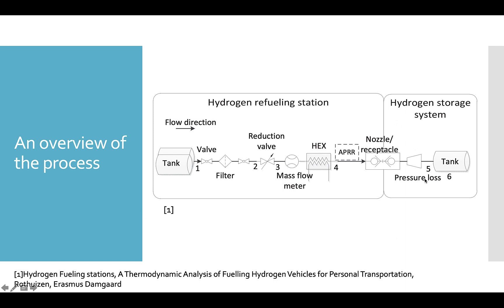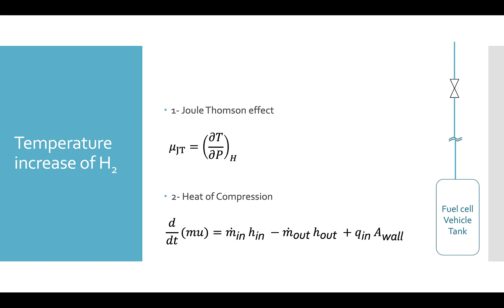In this process there are two points which increase the temperature of the hydrogen. One is in the reduction valve where we reduce the pressure of hydrogen, and the other is in the tank where we're increasing the pressure of the hydrogen. There are two contributing factors to this temperature increase: the Joule-Thomson effect and the heat of compression.